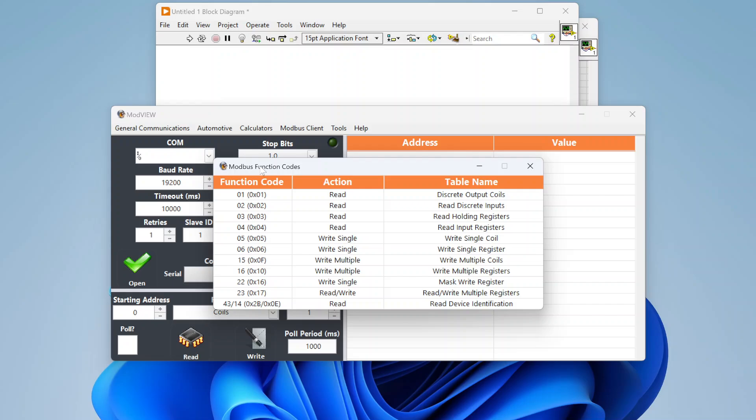Per your device, you'll need to read the manual to see which function codes it actually supports. Your manual will also include a list of addresses where specific data is stored. For example, a flow meter using Modbus might have holding registers for current flow data, max flow, min flow, average flow, fluid temperature, status information, and error information — all at specific addresses that vary from device to device.